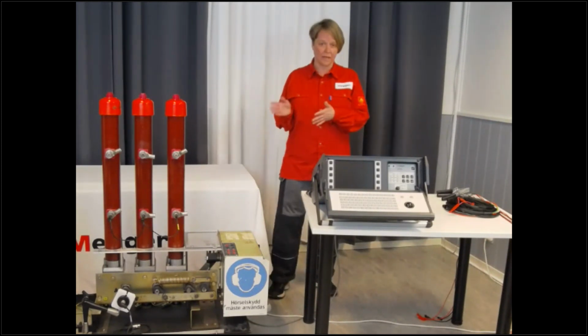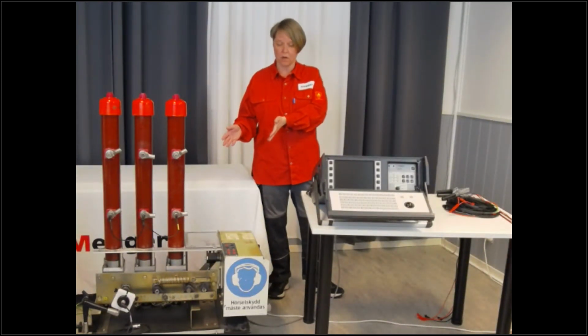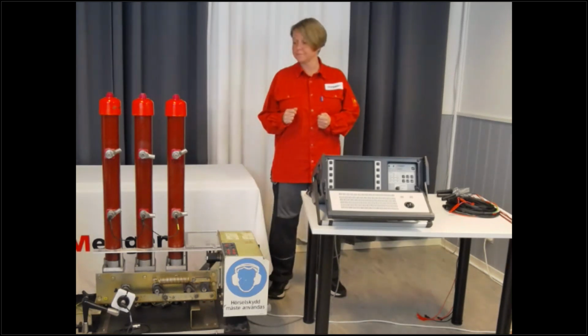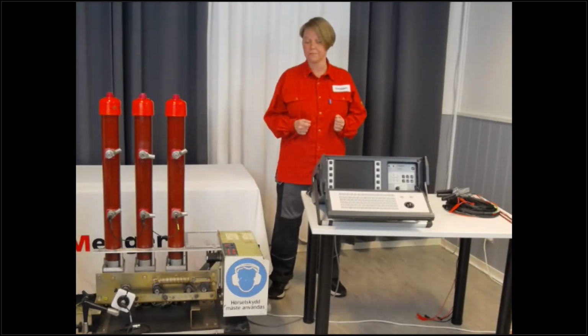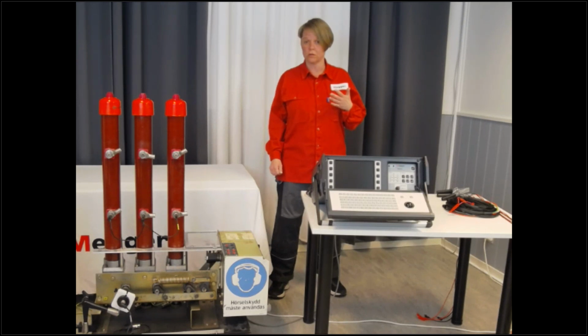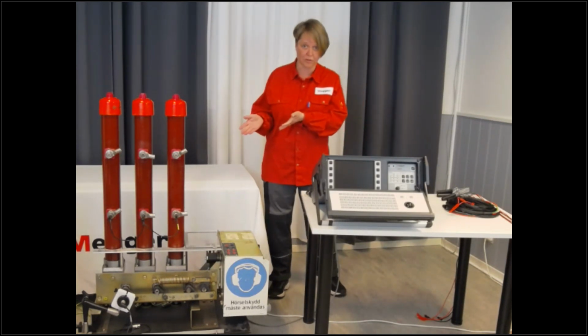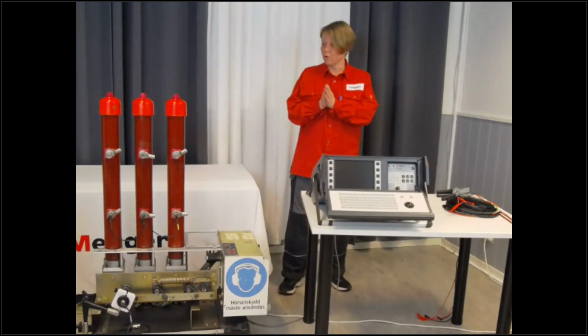This is a bit odd here because my object is not connected to any switchgear at all. It's, as you can see, on a truck, just pulled out. So I have to do a sort of fake grounding to simulate this. That technique is more for outdoor breakers where the circuit breaker is connected the whole time. I want to mention before we start that you of course need to follow all local instructions regarding safety. As I said, the circuit breaker here is not connected, so it's not really the same situation. But let's get started.